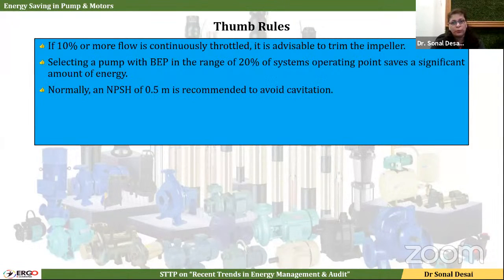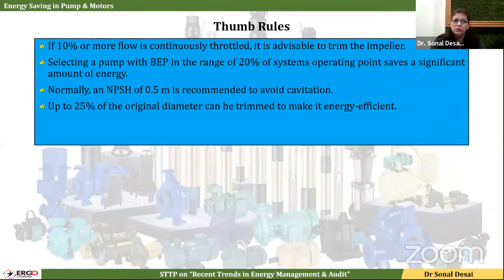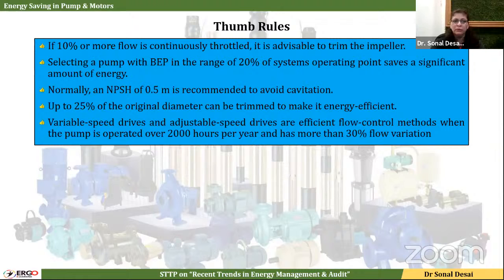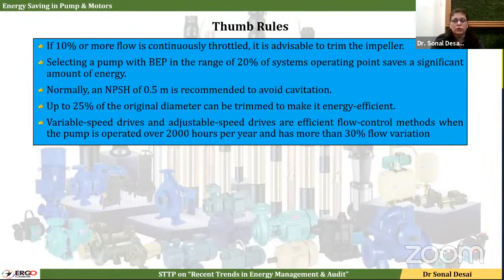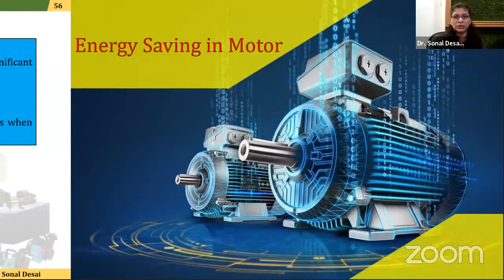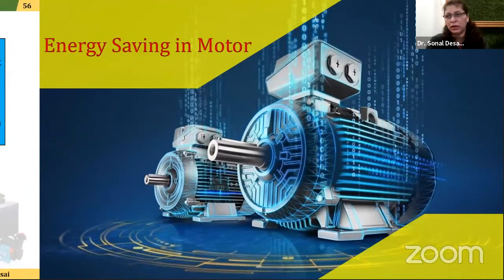Normally, NPSH margin of 0.5 meter is recommended to avoid cavitation. Up to 25% of the original diameter can be trimmed for the impeller. And variable speed drives are always advisable when there are 2000 hours of annual operation, or there is 30% flow variation. So this was all about energy saving in pump. And now going to the next topic, that is energy saving in motor.